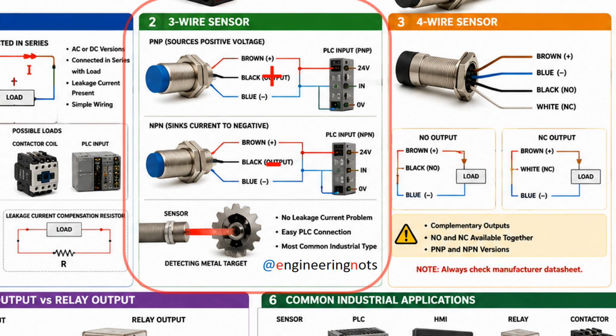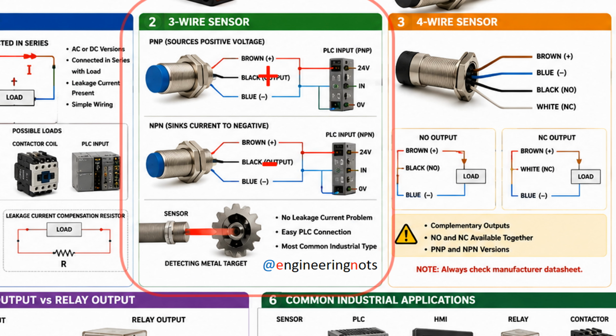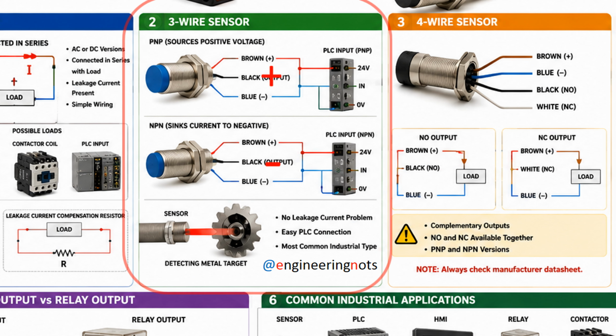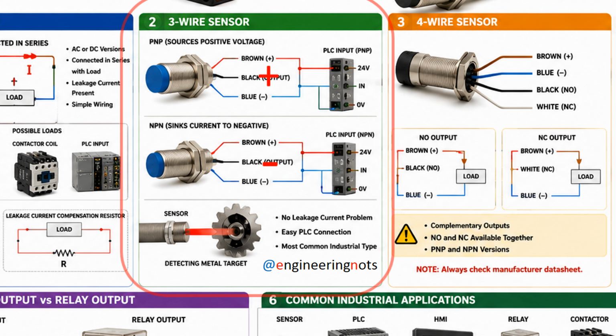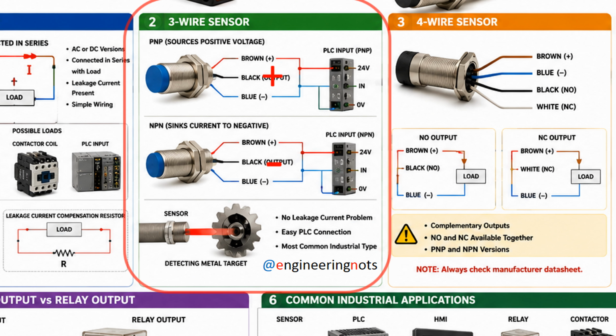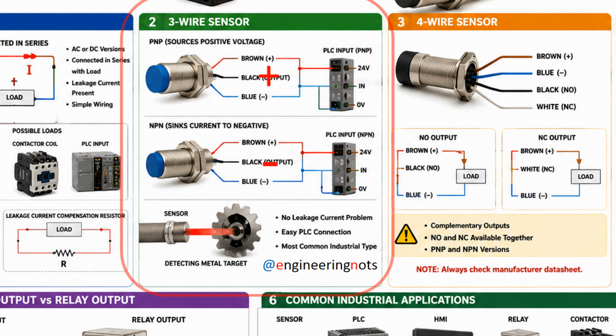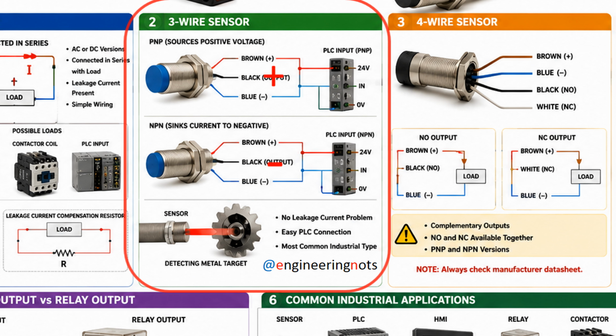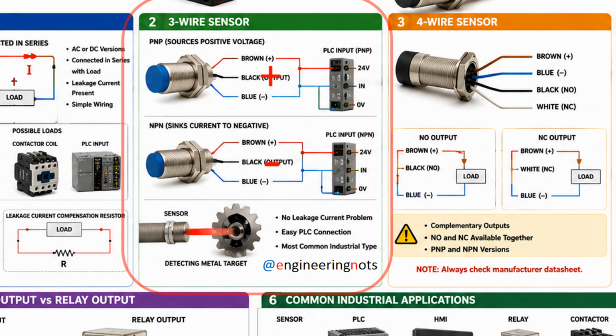What is PNP? In a PNP sensor, when the sensor is activated, the positive voltage is supplied to the load. For this reason, it is also called a sourcing output. What is NPN? In an NPN sensor, when the sensor is activated, the output is connected to the negative side. For this reason, it is called a sinking output. Which one is better? From a functional point of view, both types work correctly. However, in many European countries and modern industrial systems, PNP sensors are more common. Many modern PLCs are also designed to work with PNP sensors.